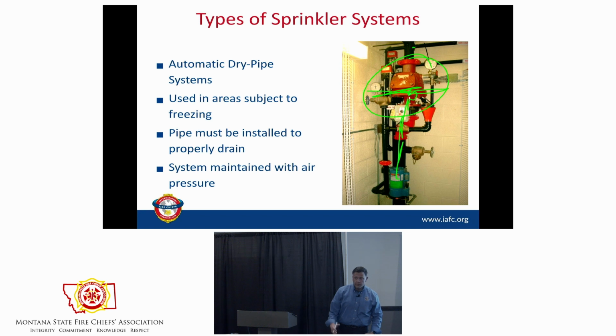Why? Freeze, right? So if we see it's tripped, number one, assume a fire and get your rears up into the attic and make sure we don't have a working fire, right? But number two, if we don't see a working fire, we have no smoke conditions, it tripped. Now, how do I know it tripped? Well, if we look on this riser, one thing that's different with a dry pipe, we have gauge, oh boy, you can't even see that. We have gauge number 1 and we have gauge number 2. What do the gauges do here? Okay, they're equalized if they're tripped. So one's measuring water pressure up to that valve, and one is measuring air pressure. But once the air is going out, it's measuring what?